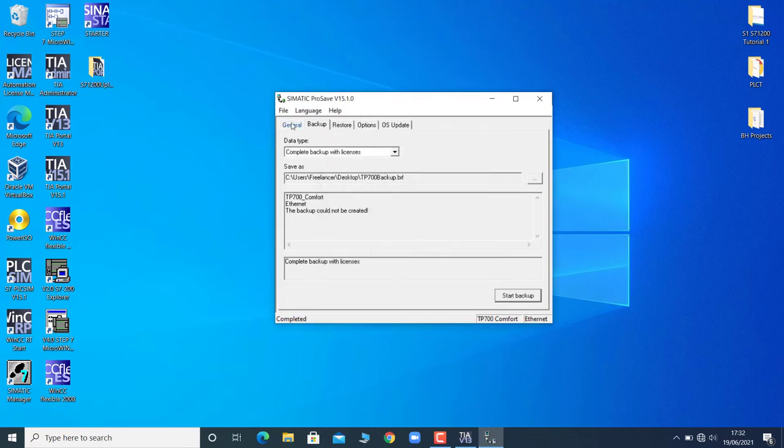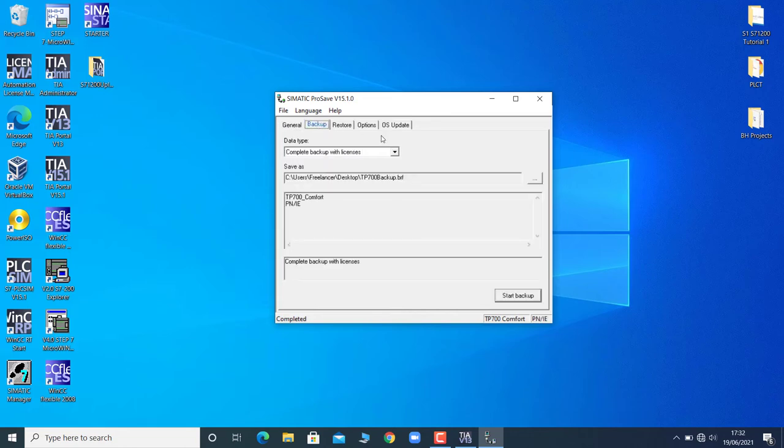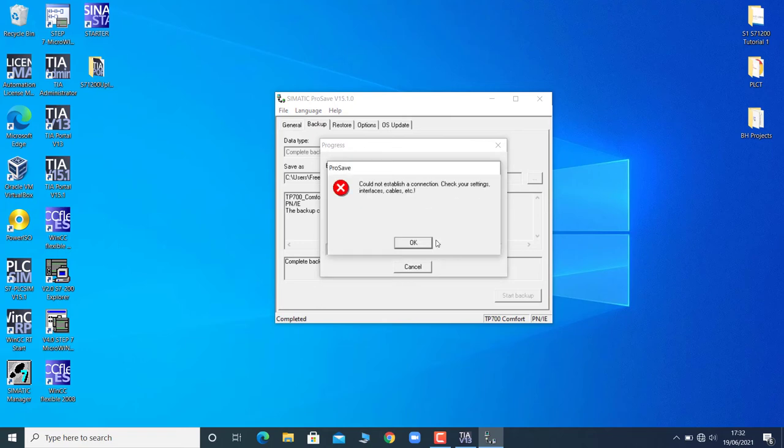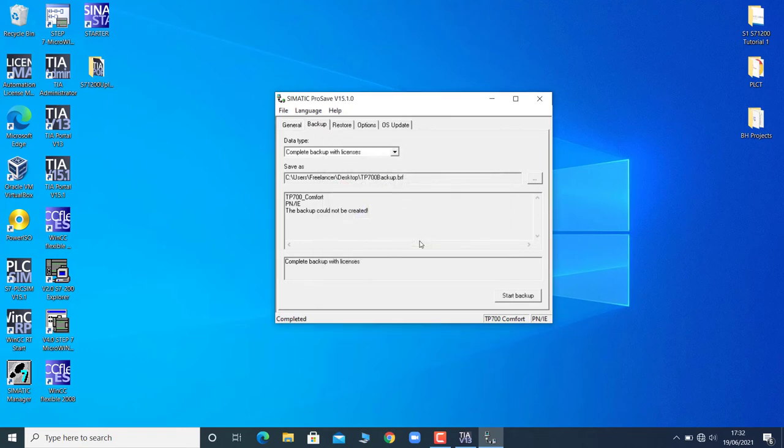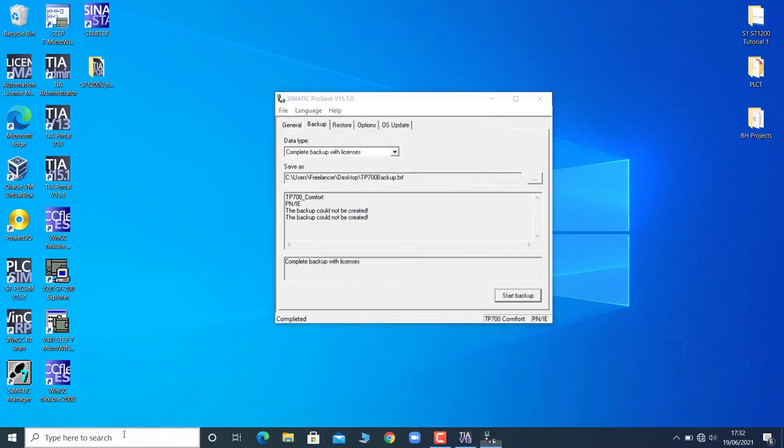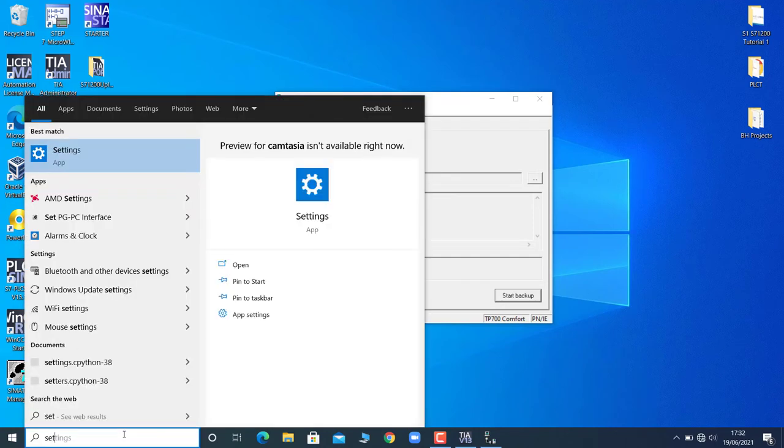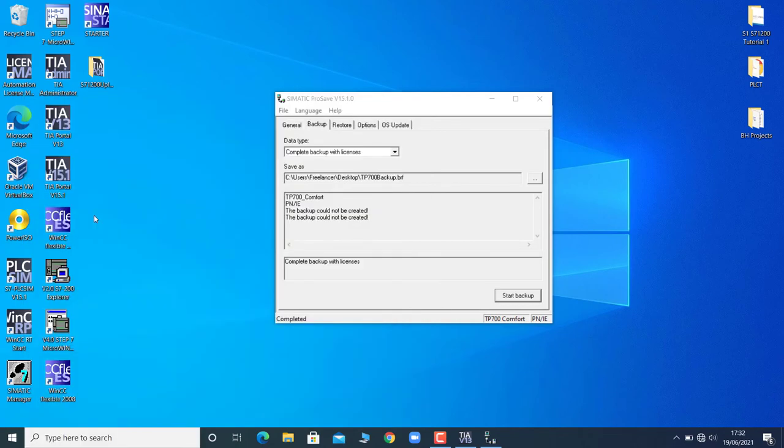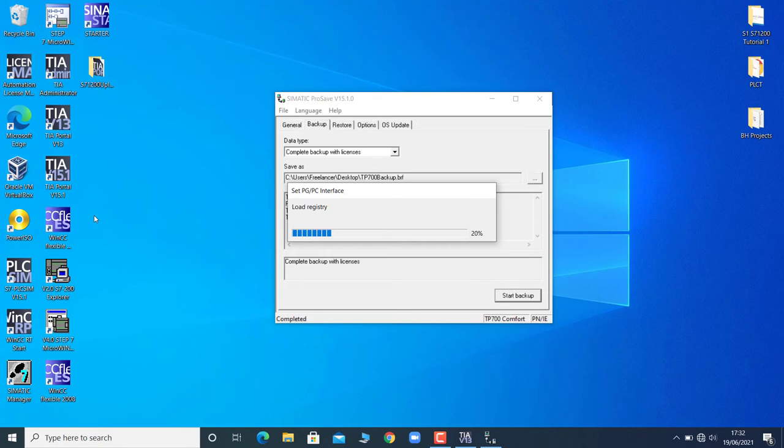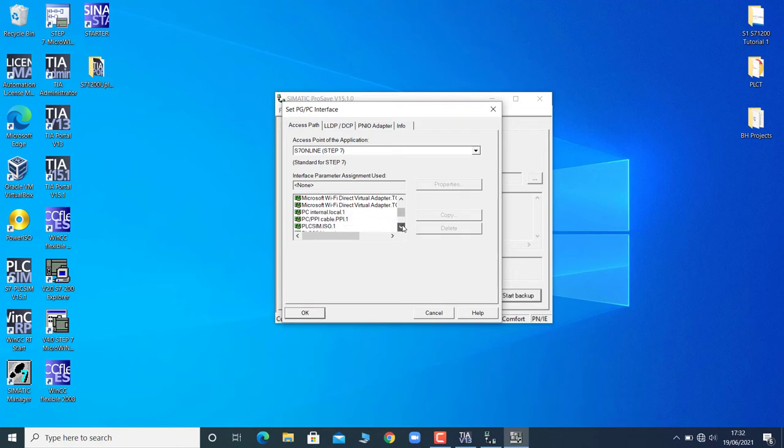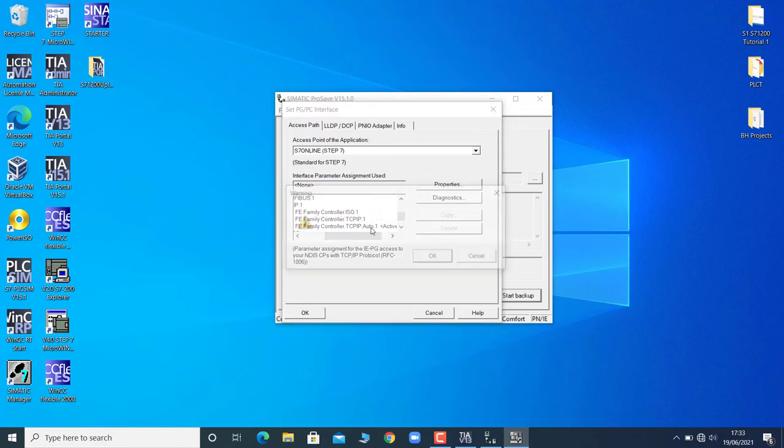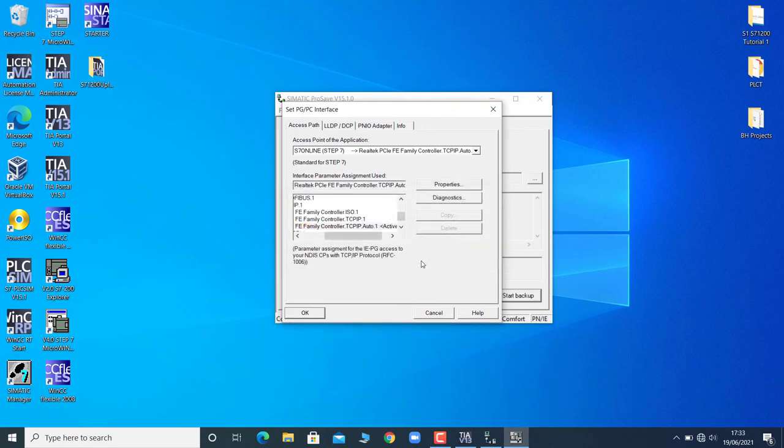So I will go back and I will change the connection mode to the PROFINET/Industrial Ethernet. Still it is giving an error, so the next step is to go to the setting of the PG/PC interface in control panel. I will go to the set PG/PC interface, and over here I will select the active connection interface - that is the TCP/IP auto mode - and click OK.